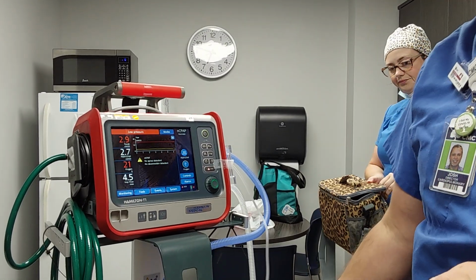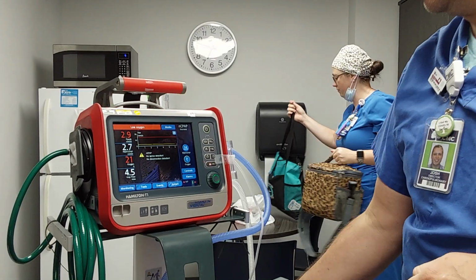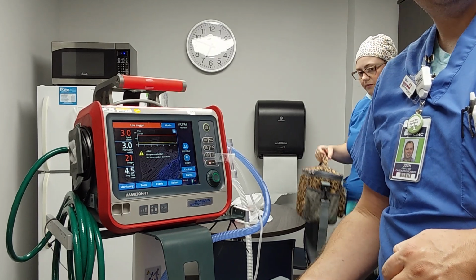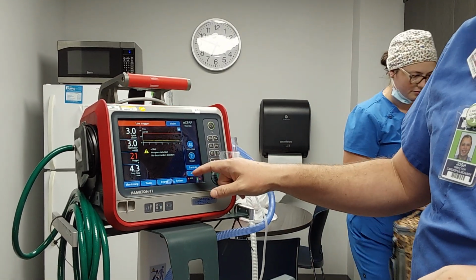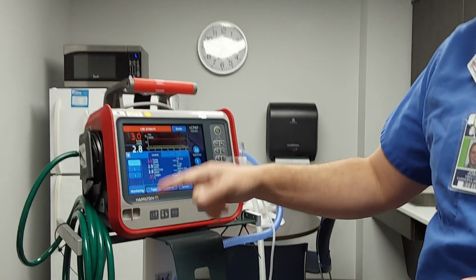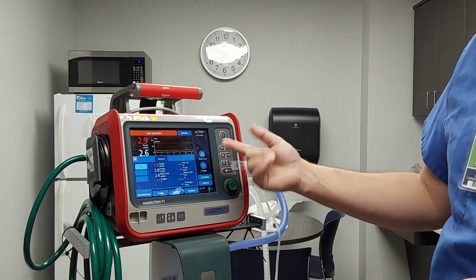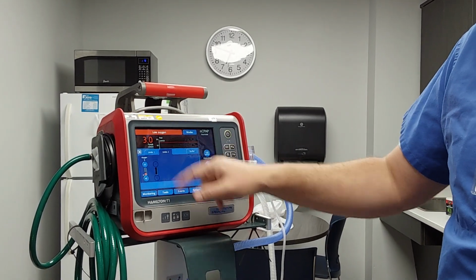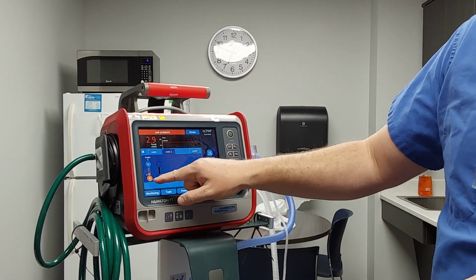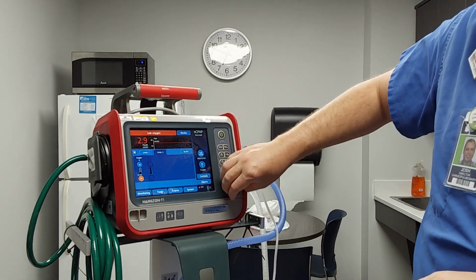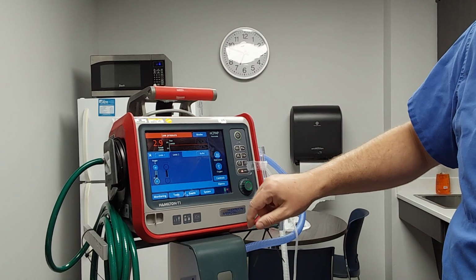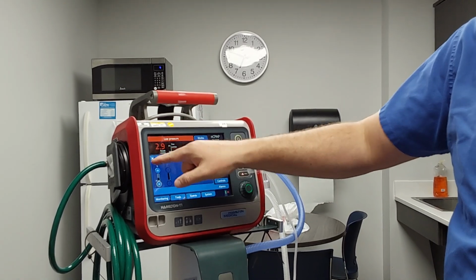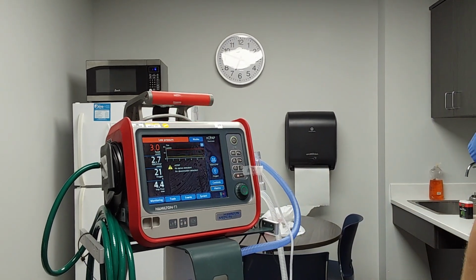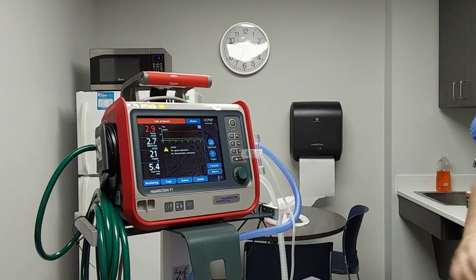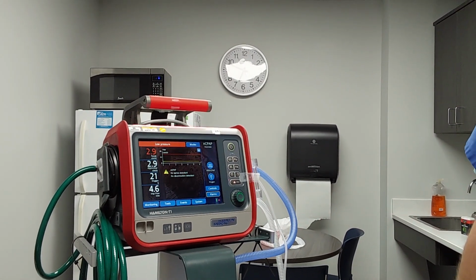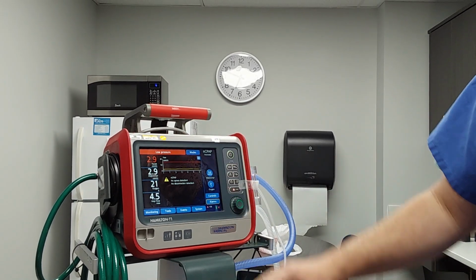And then if you're still getting this alarm, like this low pressure alarm, our humidifier is open right now, so we're losing pressure right there. Remember your low O2, if you're getting that, we shouldn't be getting that. Set at 21, so I'm not sure why that's alarming. We can go in and look at that. The alarm is set at 25, that's why it's alarming. The low pressure, it's because we have leaks in our circuit. Right, because of it being open, plus, like you say, with no water on there. Okay. So any questions about the CPAP mode?